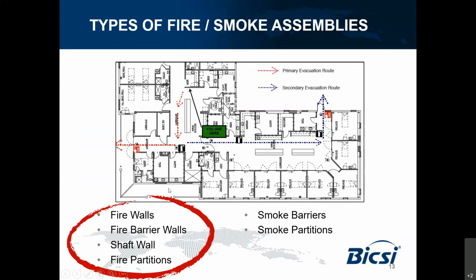Fire rated wall, fire barrier wall, shaft wall, fire partition — those terminologies, when you hear about them, basically mean that wall needs to have fire stopping material provided when you pass through it. Some people may challenge, 'my cable just goes through a normal partition wall' — for those cases, you may or may not require fire stop. It really depends on what the wall requirement is. If the wall, when designed, is a fire partition rather than a normal partition, you need to handle it.